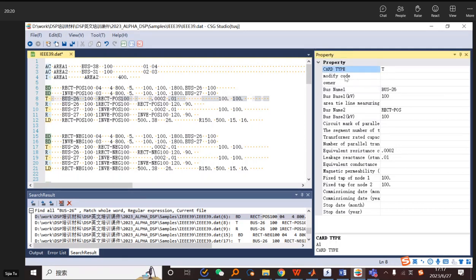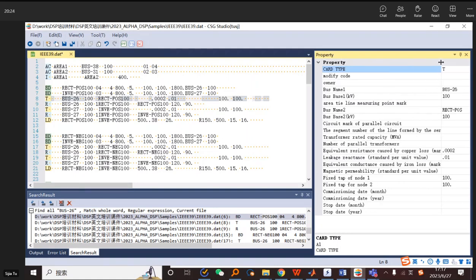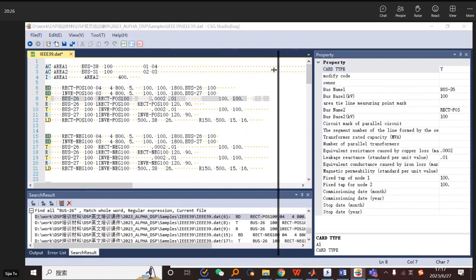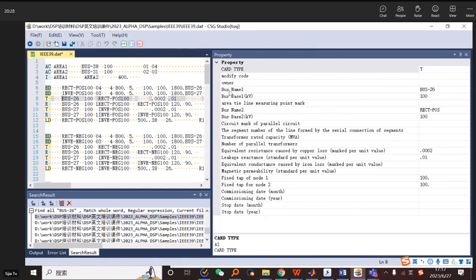In the T card, you can see all the parameters you should write. For the transformer, the two terminals mean bus name 1, bus name 2, the bus voltage 1 and 2, the resistance, reactance, and fixed tap of node 1, node 2.